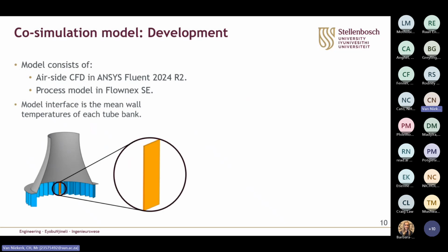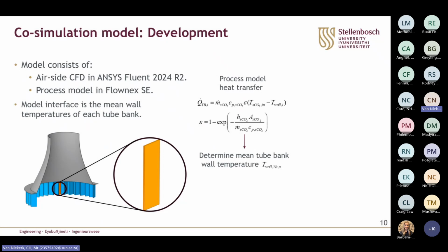So to illustrate this, we'll just consider the heat transfer modeling of a single tube bank situated around the tower. The sCO2 side, solved by the discretized element-based model, uses the effectiveness-NTU approach to determine the heat transfer. Here, the convective heat transfer for a single increment along the flow path of a tube bank is solved from the incoming sCO2 to the tube wall. Using this approach, we can accurately capture the logarithmic variation of temperature through the heat exchanger, and after that, we can then determine the mean tube bank wall temperature of that individual tube bank.